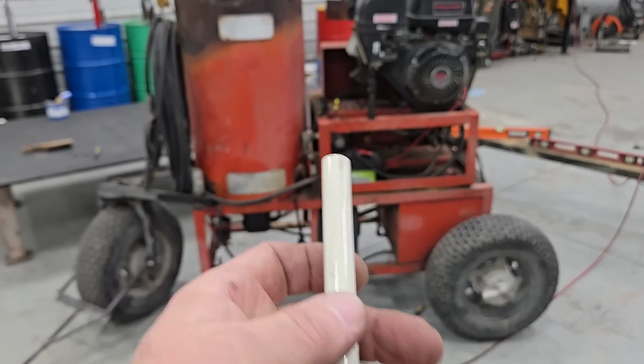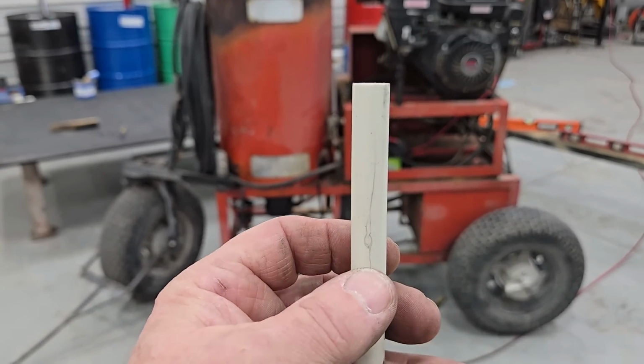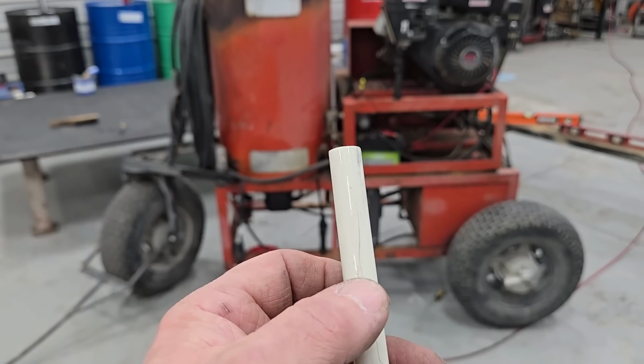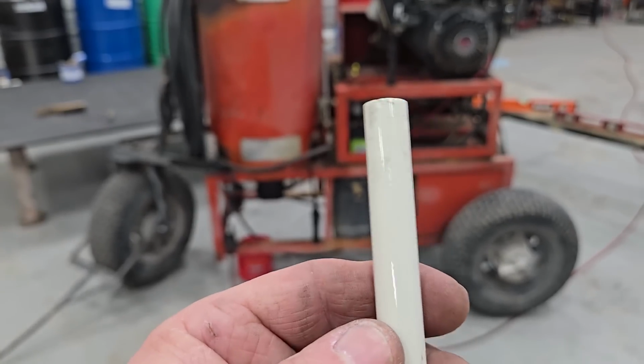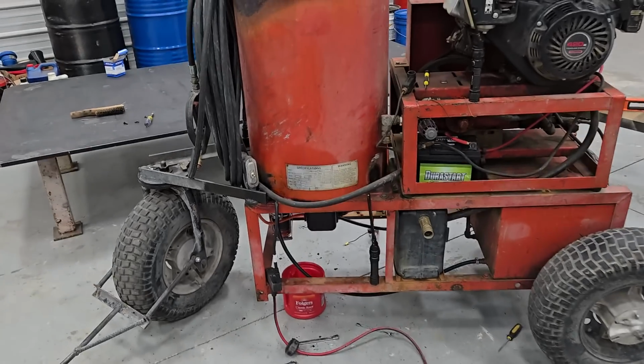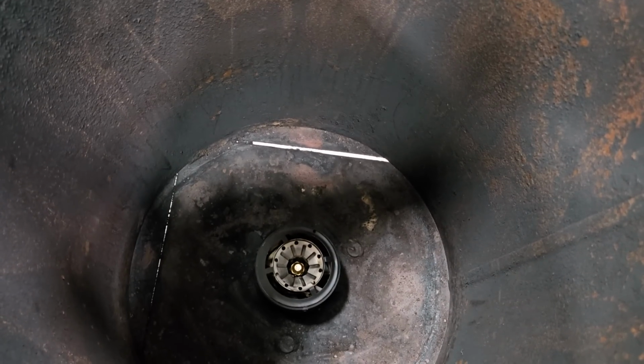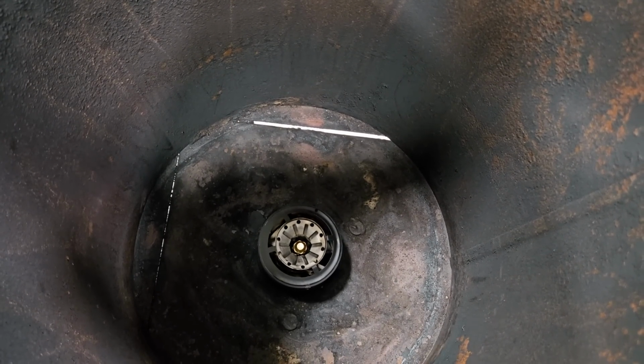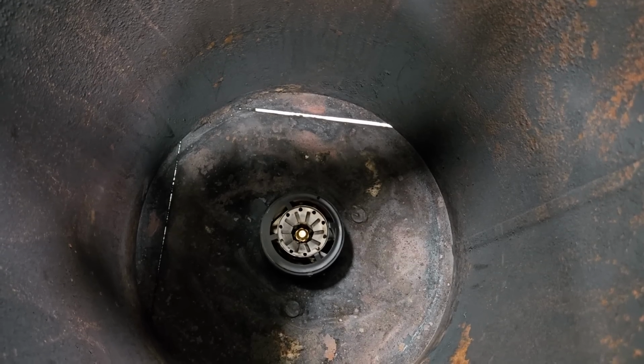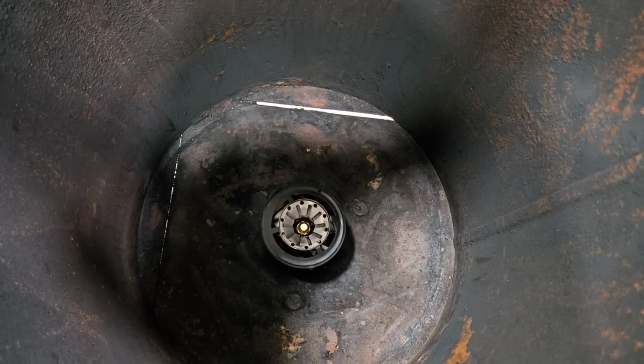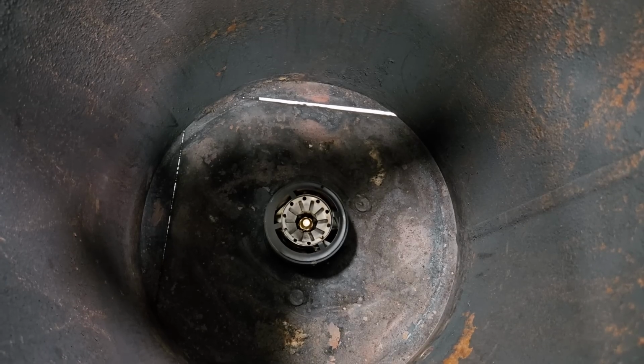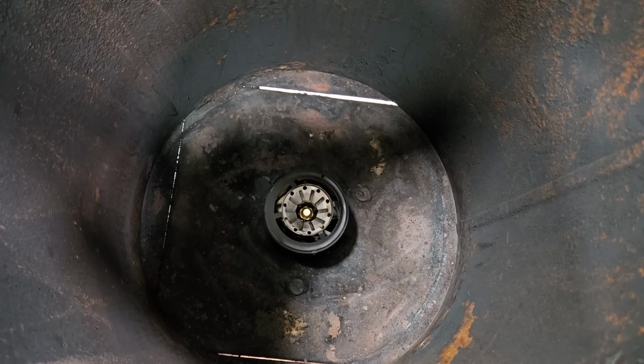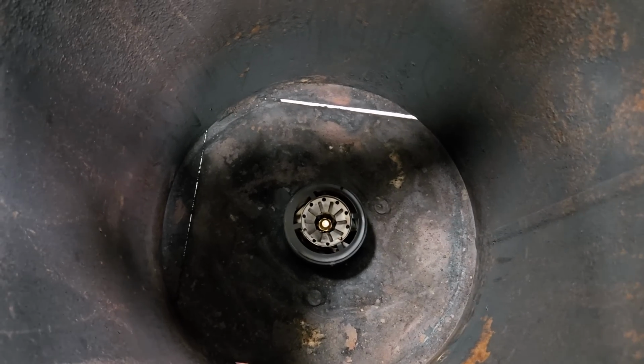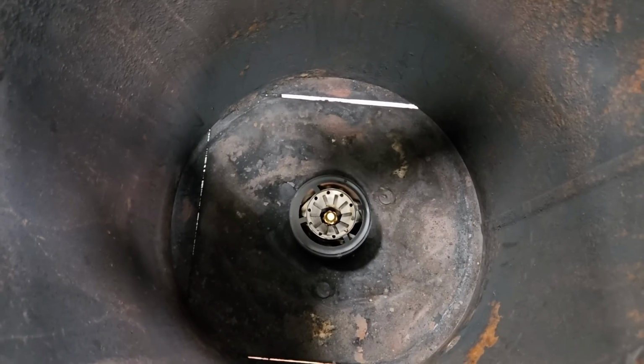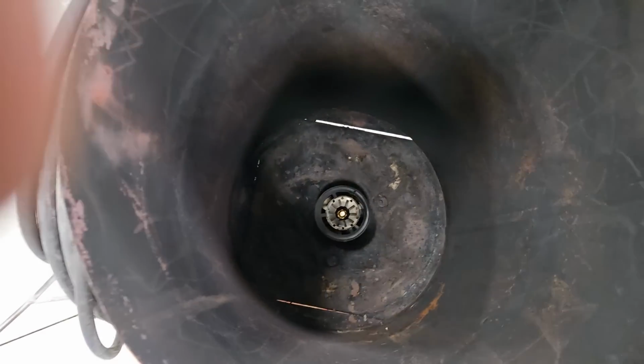I took the burner unit out and was trying to readjust the electrodes, and I tightened it down too tight, and I broke this one. Then I had no spark. So I put the old ones in and adjusted them, and I noticed my spark was coming up and making contact with the bottom of that flame cone. So I lowered the nozzle assembly down just a little bit and tried it again, and it fired, and it fires every time. Let me show you what we got going on here.